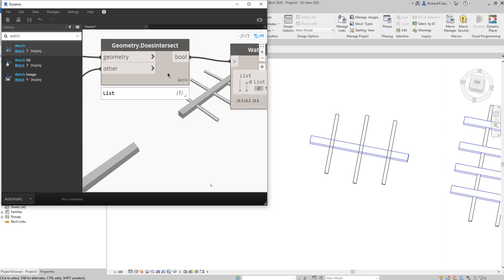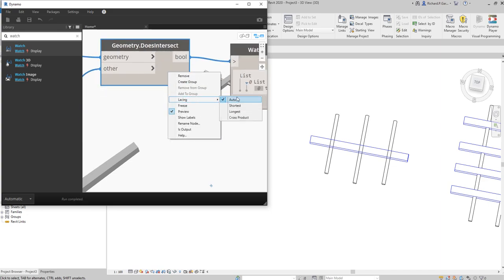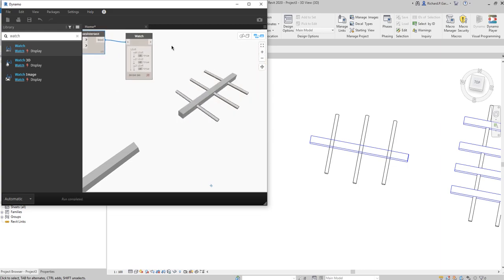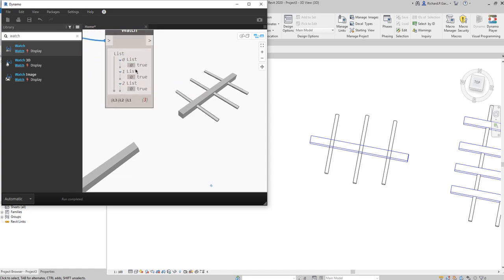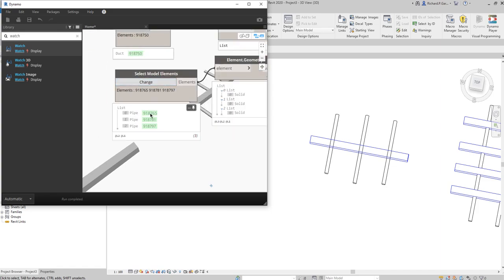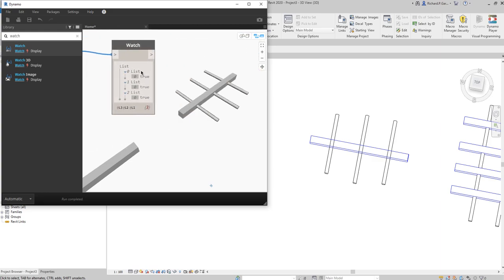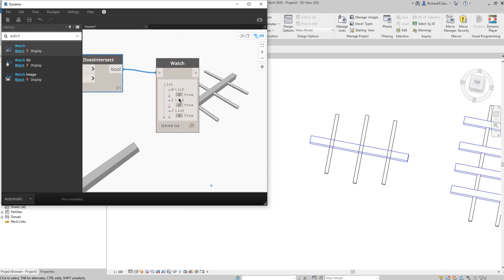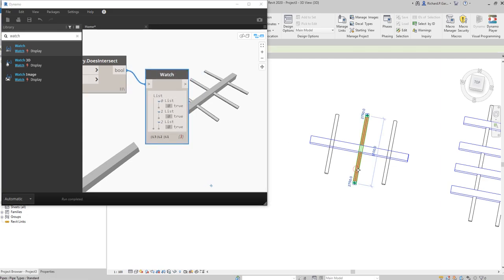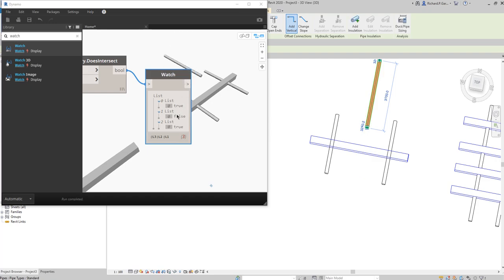Now I'll change the lacing. Right-click the DoesIntersect node and instead of Auto or Shortest, select 'Longest'. Now we have three outputs. Dynamo checks the intersection between the duct against all three pipes — duct against pipe zero, duct against pipe one, duct against pipe two. The output is true, true, true — all are intersecting.